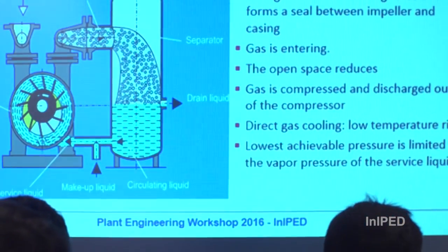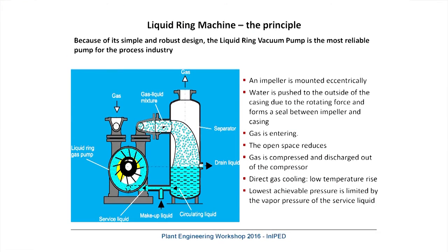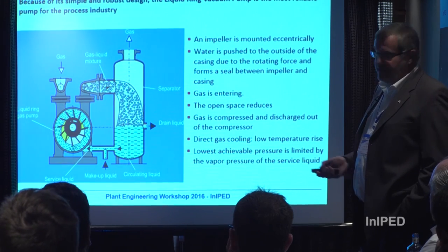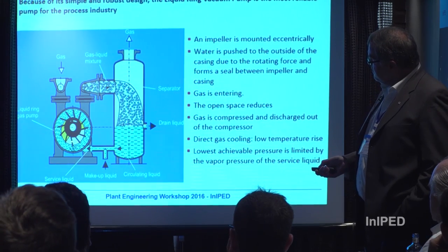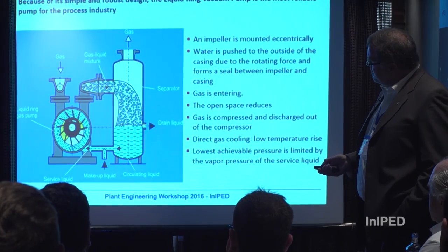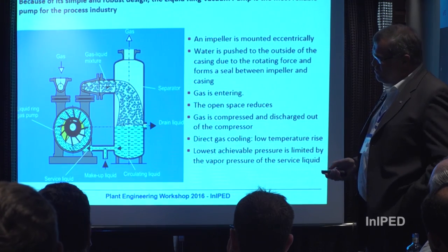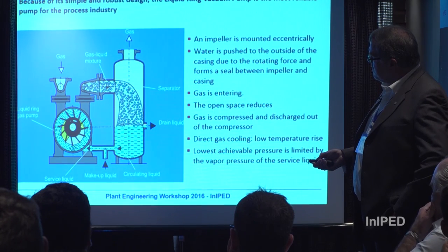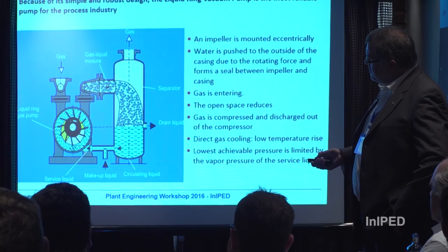Working principle. A very simple picture shows how the machine runs. An impeller is mounted eccentrically in the casing, and due to the rotating forces, the service liquid is pushed into a ring concentric to the casing. When rotating, there is an opening volume between the impeller blades, the liquid ring, and the hub — so in this stage the gas is sucked in due to the increasing volume. Then the gas is compressed, and as the gap gets closer and closer, the gas is discharged.